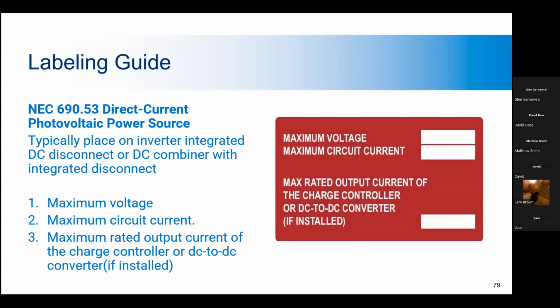Next, we have the direct current PV power source label, and that has to be on an inverter integrated DC disconnect or a DC combiner with a disconnect. It gives important system information to those who will maintain and repair the system in the future. You have to include the max voltage, the max current, and the max current of charge controllers if it's installed with energy storage.